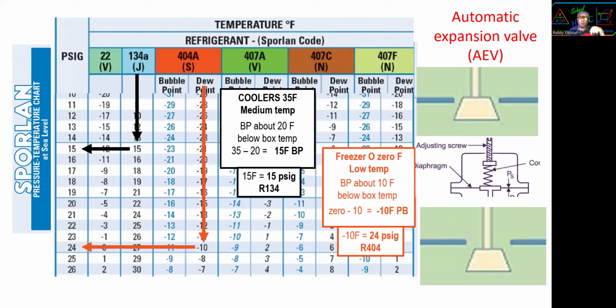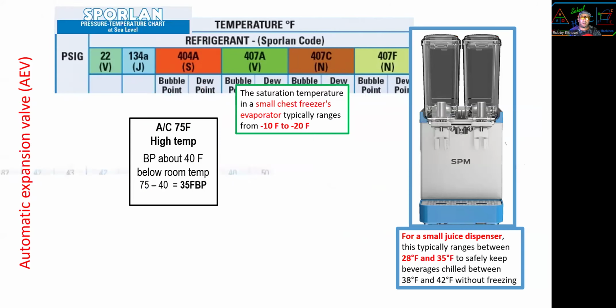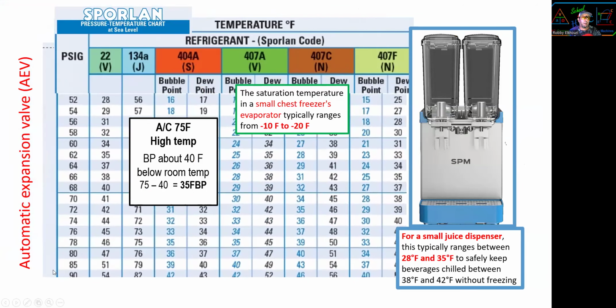I guess think about it now. We adjust it down, right? It would let more pressure in. Pressure should go up. You adjust it up, then it should restrict and pressure should go down. Okay, and it's very common for air conditioning, 35 degree, but you're not going to see automatic expansion valve on air conditioner, though. A bad example. Saturation temperature on a small chest freezer evaporator between negative 10 to negative 20, correct? Small juice dispenser, 28 to 35. Beverage going to be between 38 to 42.